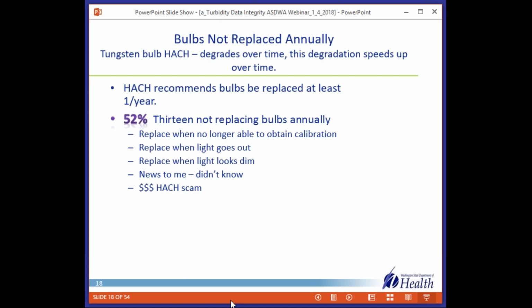Listed some here. Some systems replaced the bulb when they were no longer able to obtain calibration. Some replaced it when the light went out. Some when it visually looked dim. Some operators didn't realize that that was a recommendation from HACH. And there was a couple like, we're just skeptical of these things, you don't really have to do it. It's just another thing to get more money out of us.